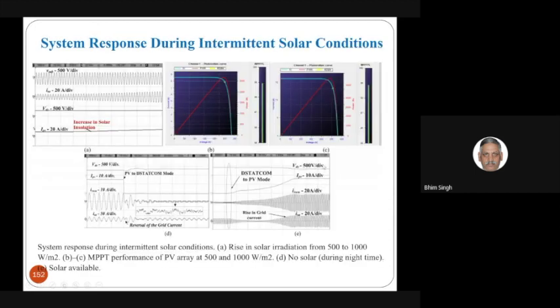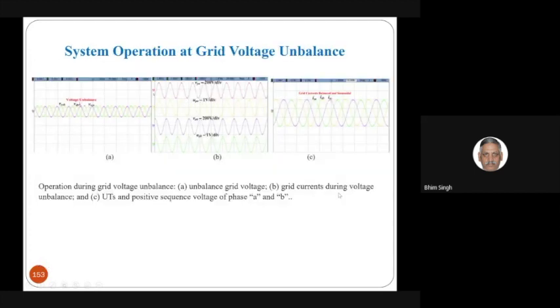And this is the case again when the PV generation is reduced to zero, it works as a DSTATCOM. I mean, to meet the harmonic requirement of the load, you can feel it as working as a filter. And when the generation starts coming again, you start working without any bus collapse and with grid current balance, under the varying solar power generation.